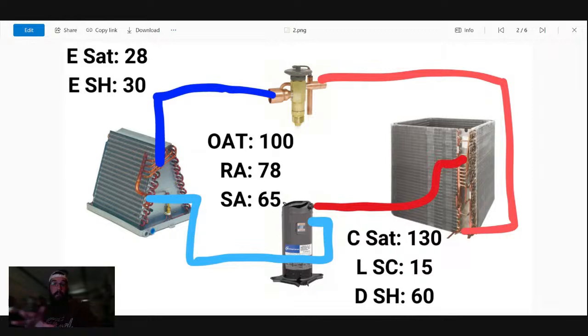In this particular case, okay. So let's summarize that. Then this will solve our non-condensable question as well. So let's say we did that process. We recovered several pounds out. We partially filled up a recovery cylinder. We took it inside and put it in a closet. Came back an hour later or 30 minutes.